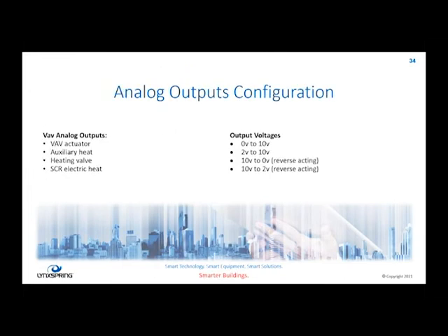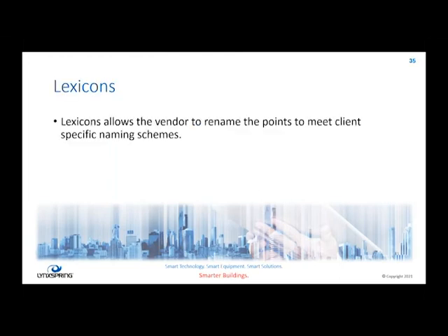Our analog outputs, we can do the actuator, auxiliary heat, a heating valve, SCR, electric reheat. So you can set it up so it's 2 to 10 volts, 0 to 10 volts, or 10 to 2, or 10 to 0, your reverse acting actuators, so that we can support any of those configurations that we run into.